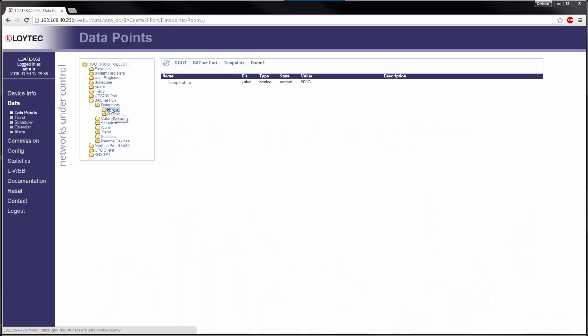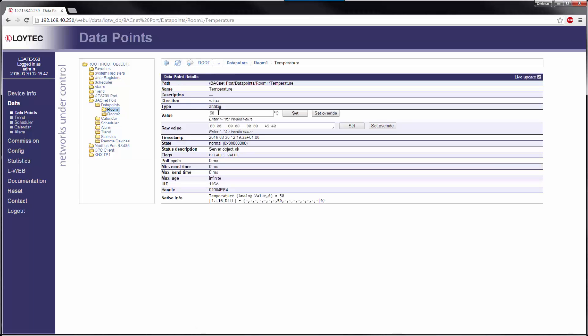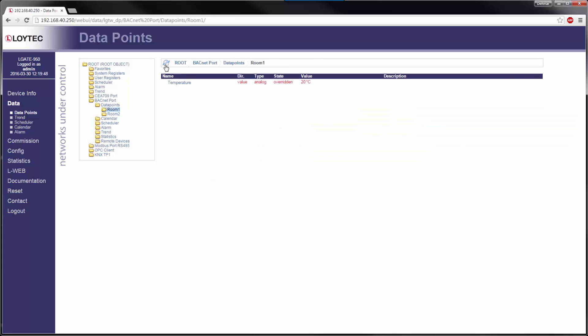The data point model in LOYTEC devices has been extended with a manual override function. On the web interface and on the LCD display, data point values can be overridden to manual values. If an override value is set, the running control logic no longer affects the data point value. Neither does network communication.